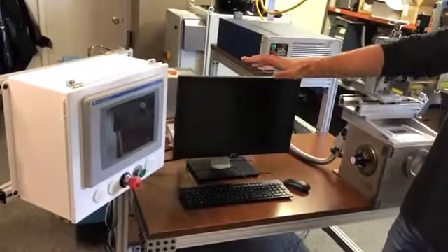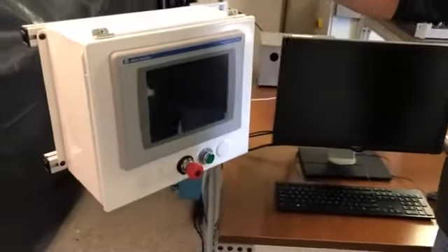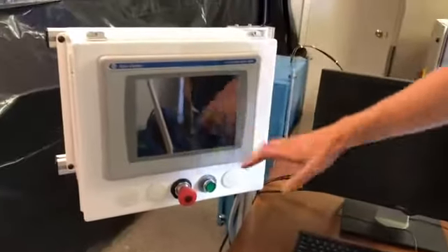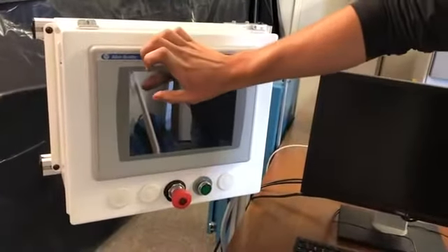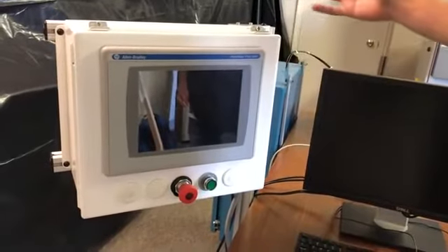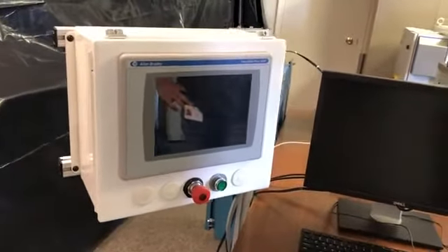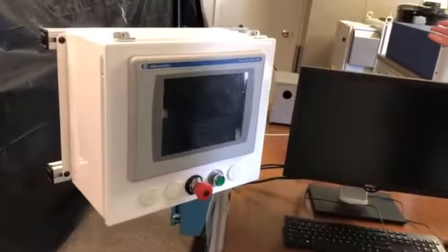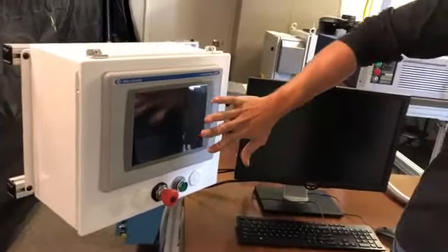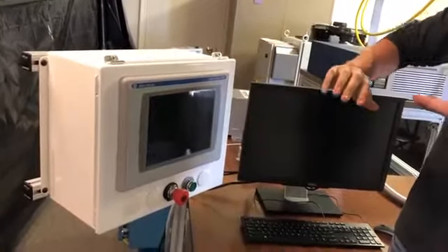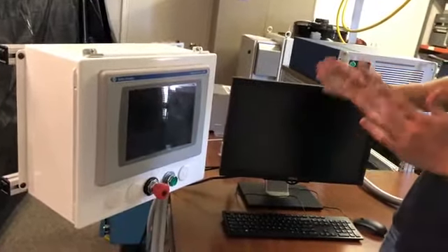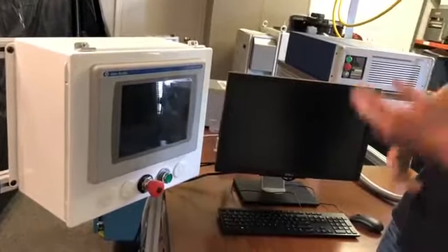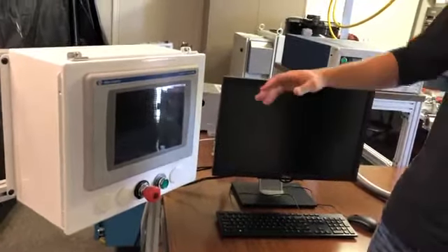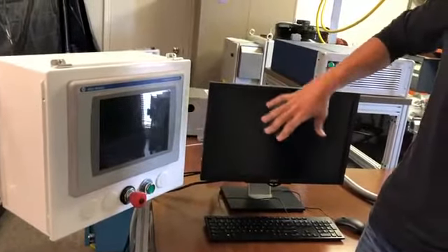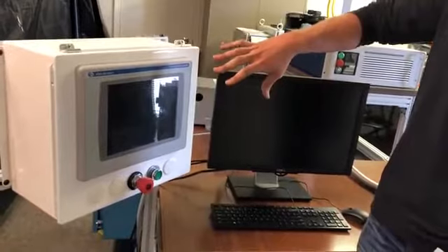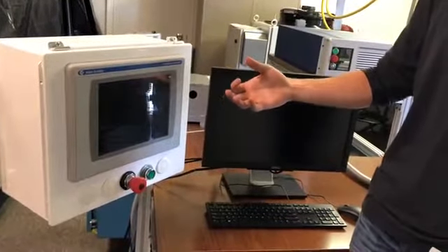As far as our HMI, as you can see, it's not necessarily powered up, but the way the program is going to work, we're going to have mainly 2 displays. We're going to have a main top bar that will have all your diagnostics, like your analog signals to and from your wobble head module and your laser generator. It will be just what we displayed, what you would normally see on a web page in regards to diagnostics, like the circle dots showing, let's say, that your emission is on, and what your power level is at. Pretty much what you would see on one of these web pages, you would more likely see on the main page of your HMI. You will then have one main screen, which you will go to select your job.